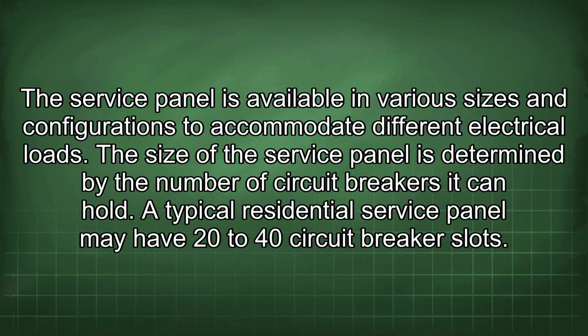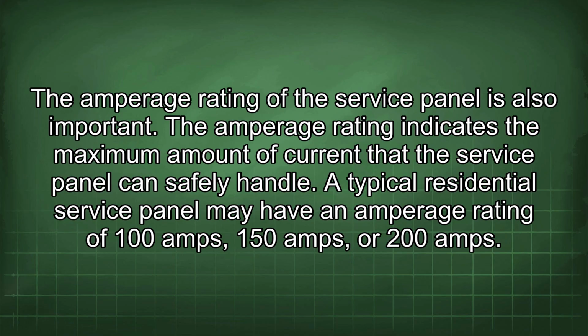The service panel is available in various sizes and configurations to accommodate different electrical loads. The size of the service panel is determined by the number of circuit breakers it can hold. A typical residential service panel may have 20 to 40 circuit breaker slots. The amperage rating of the service panel is also important. The amperage rating indicates the maximum amount of current that the service panel can safely handle. A typical residential service panel may have an amperage rating of 100 amps, 150 amps, or 200 amps.